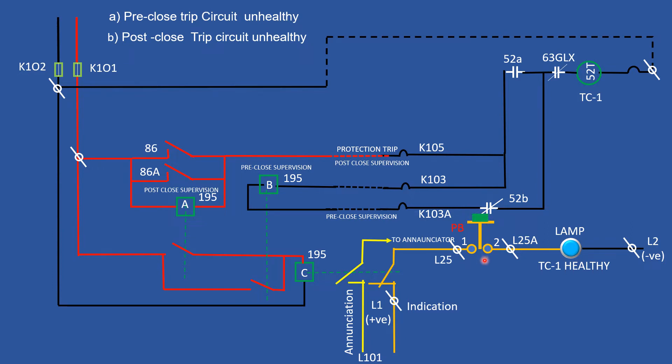Before closing a circuit breaker, L1 is connected to the circuit as positive, and L2 as negative. After pressing push button before closing the circuit breaker, the supervision relay is not energizing, which means pre-close trip circuit is unhealthy.